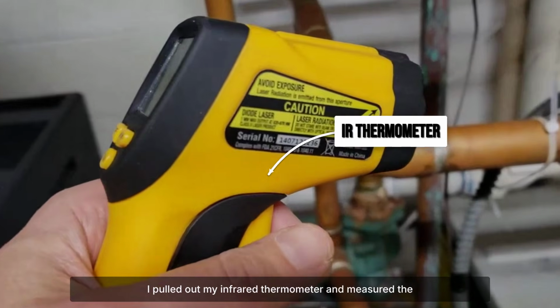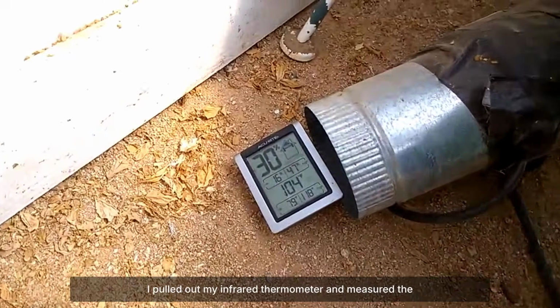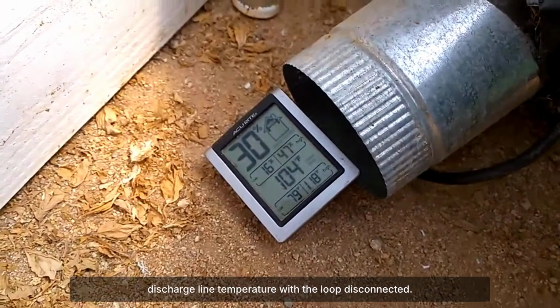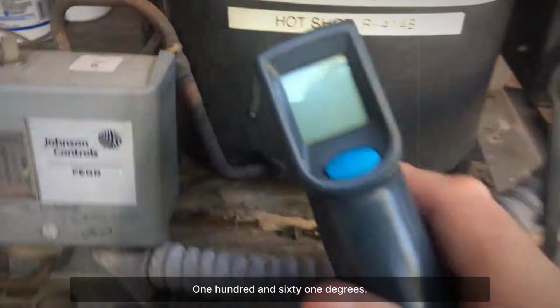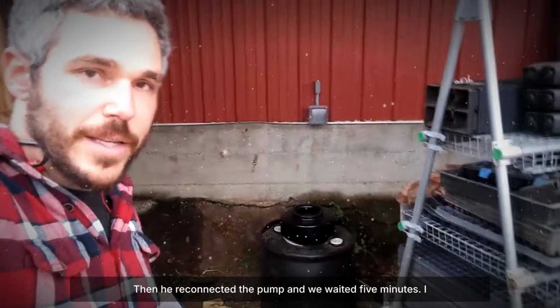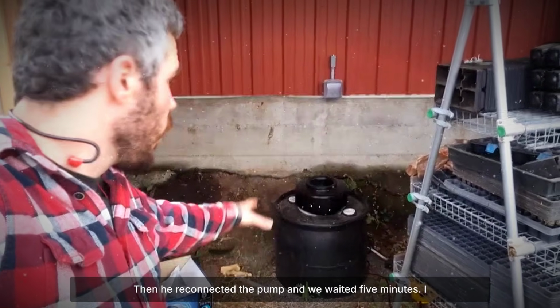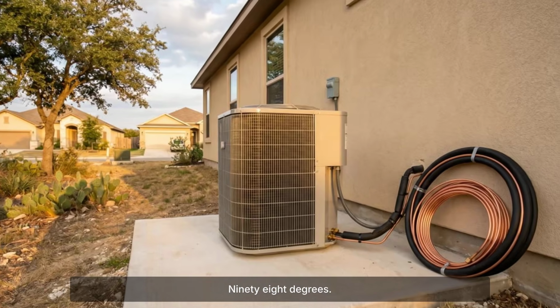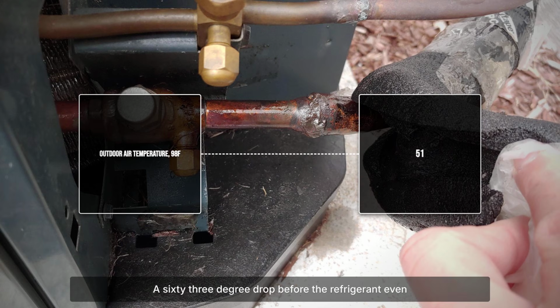I pulled out my infrared thermometer and measured the discharge line temperature with the loop disconnected, 161 degrees. Then he reconnected the pump and we waited 5 minutes. I measured again, 98 degrees. A 63-degree drop before the refrigerant even reached the condenser.